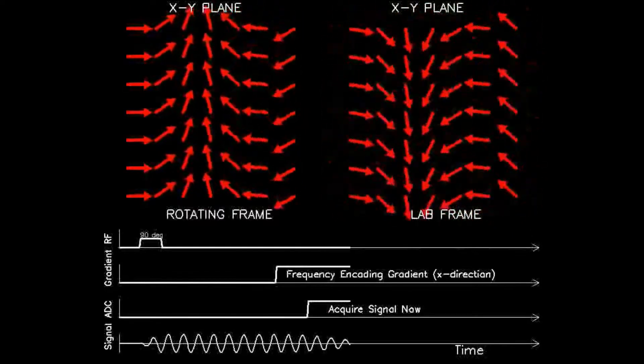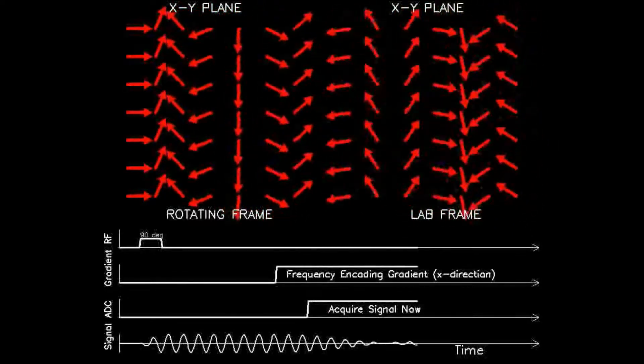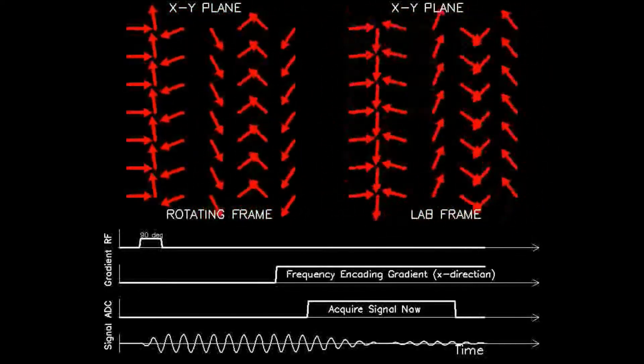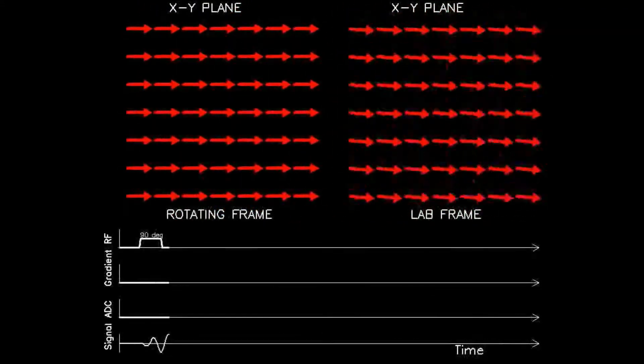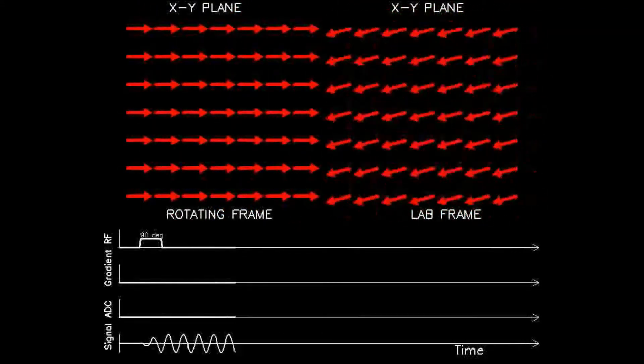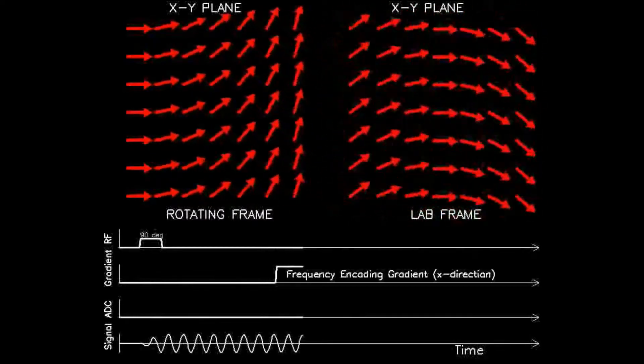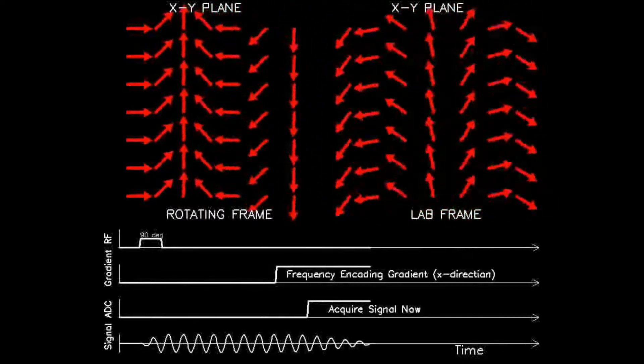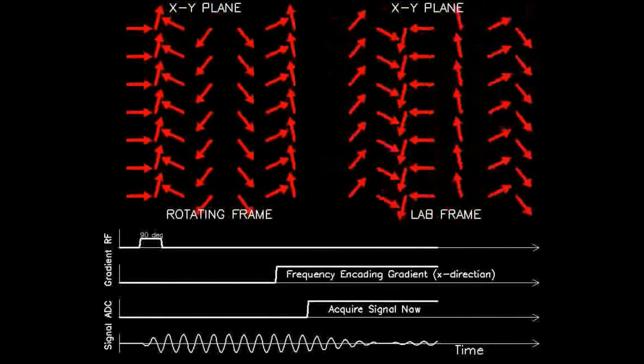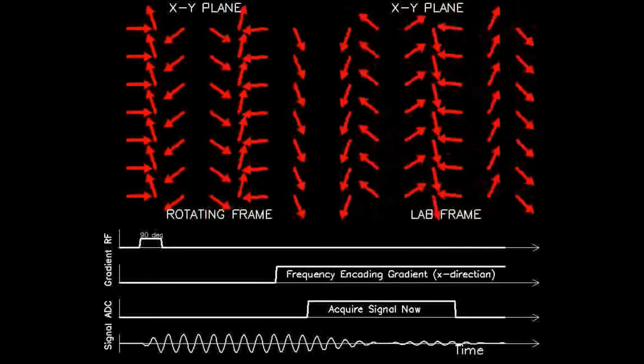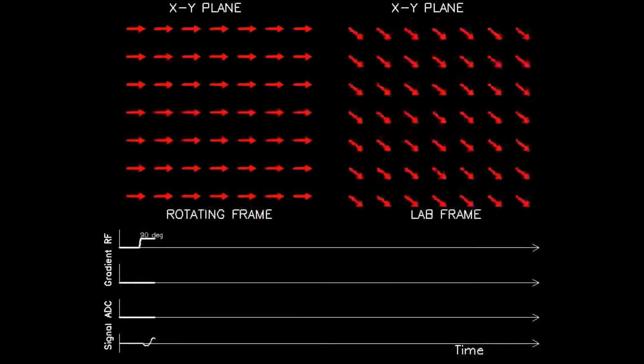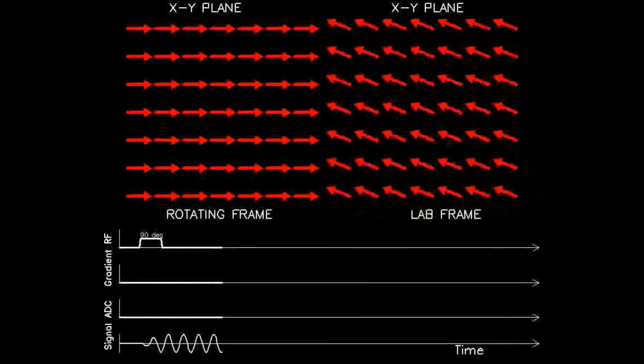The bottom panel shows a set of timelines. The top shows the RF power that causes the initial 90 degree spin flip. The second line shows application of an externally impressed gradient along the x-axis. The third timeline indicates when the detected signal is actually acquired for image processing, and the bottom timeline shows the detected total signal.